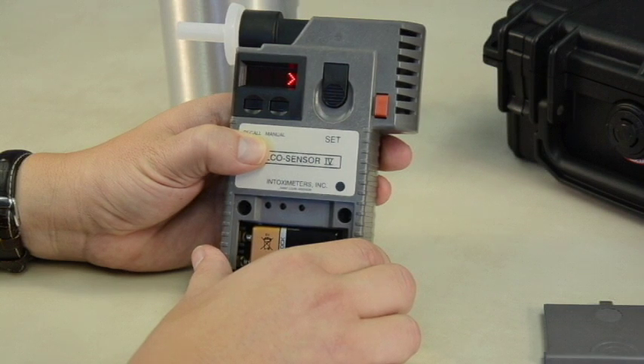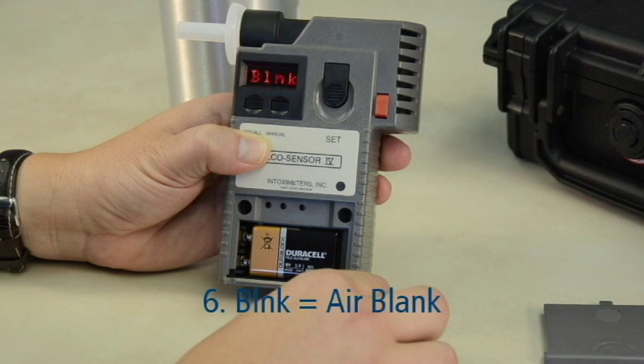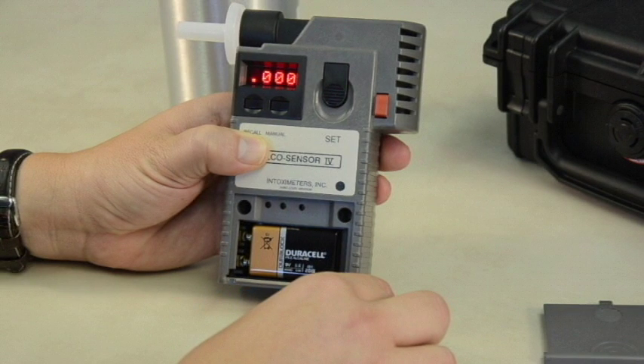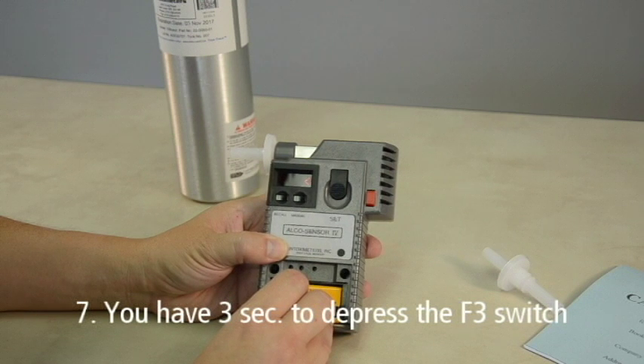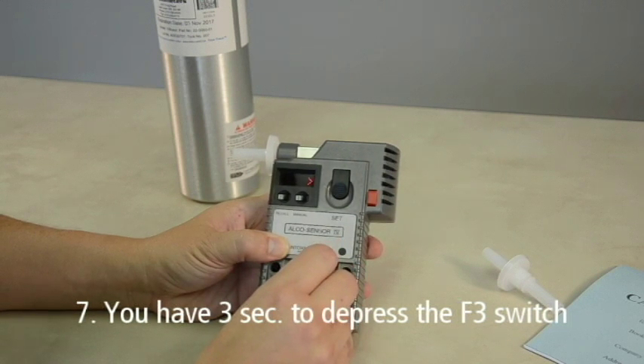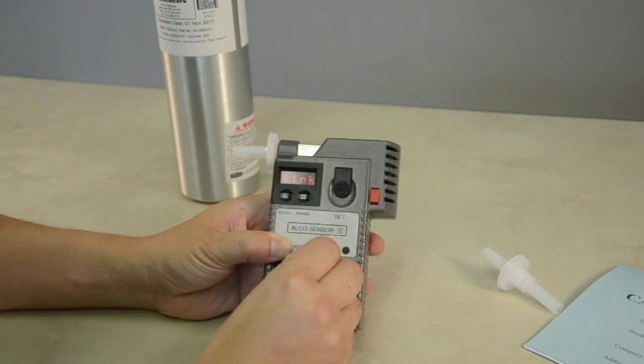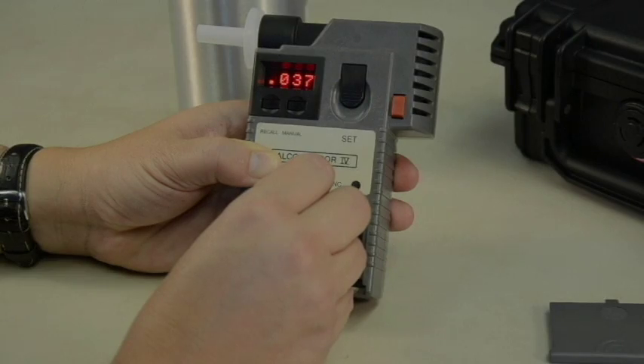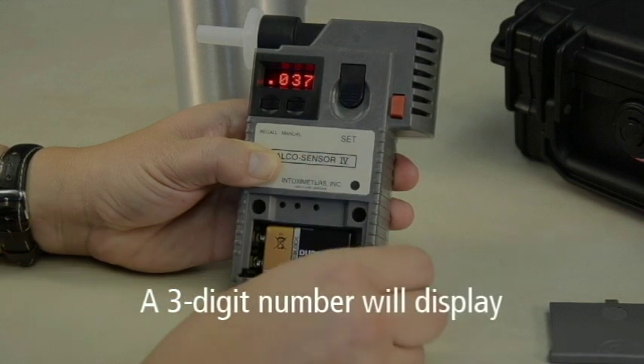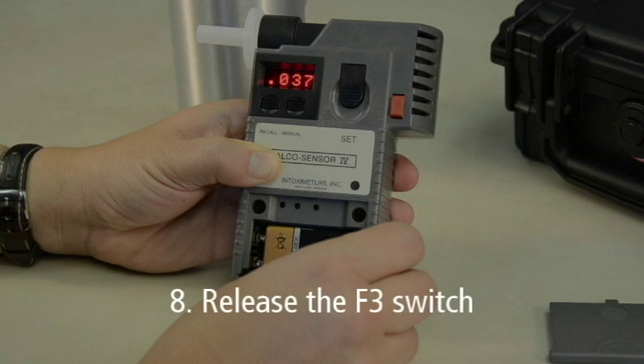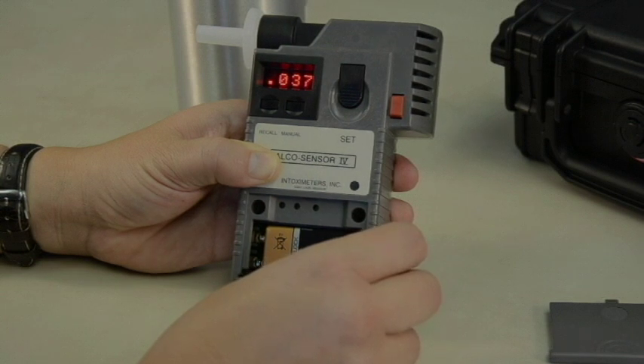Next, the device will display BLNK. This means the instrument is performing an air blank on the device. An air blank is a procedure that checks the device for any residual alcohol that may remain from a previous test. If the instrument is free of alcohol, it will read 0.000 for a few seconds. As soon as the air blank result displays, you will have 3 seconds to depress the F3 switch, or the calibration procedure will be canceled. Once the F3 switch has been depressed, a 3-digit number will display. Release the F3 switch. This number is the value of the gas standard used from the last calibration performed.